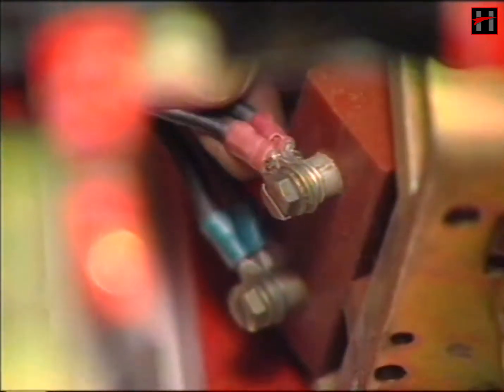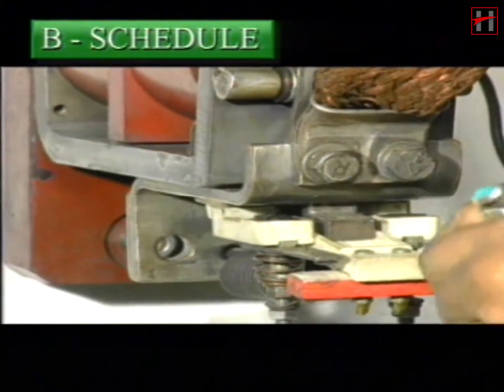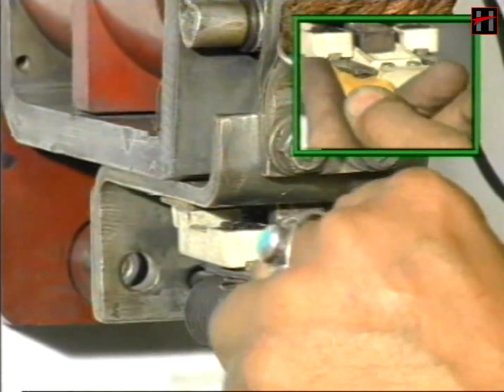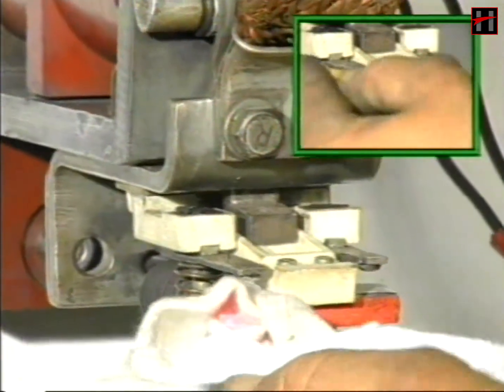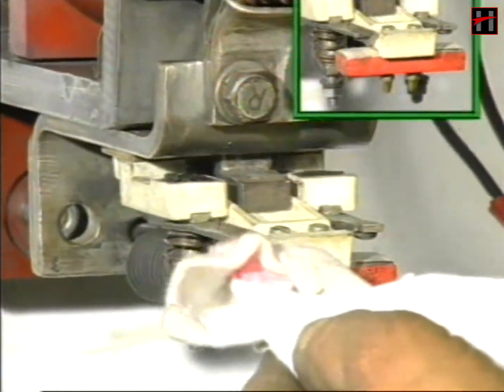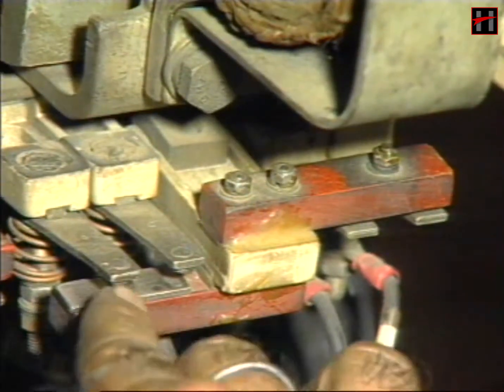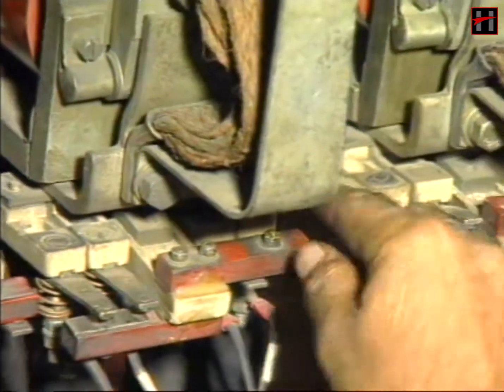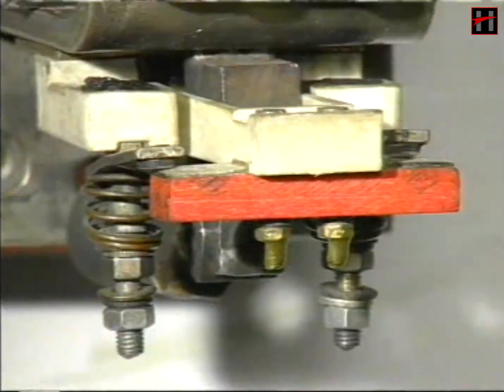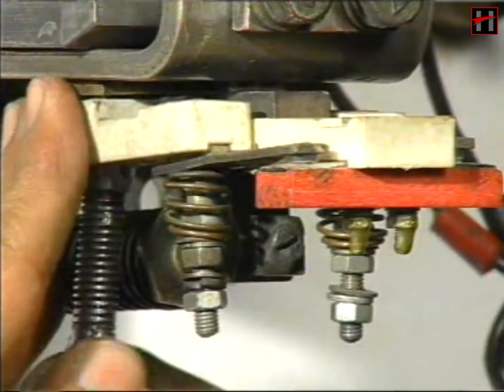Ensure that all the screws, wire terminals and foundation bolts of all the contactors are completely tightened. If any wire terminal is broken, rejoin the wire or change the terminal. In the B schedule of electromagnetic contactors, clean all the interlocks with dry and clean cloth. Check the condition of interlocks. If any interlock is broken, misaligned, or has insufficient over travel, change the interlock.